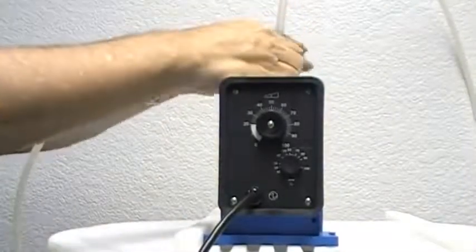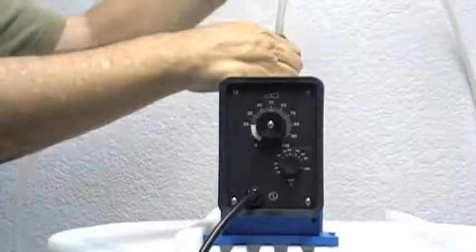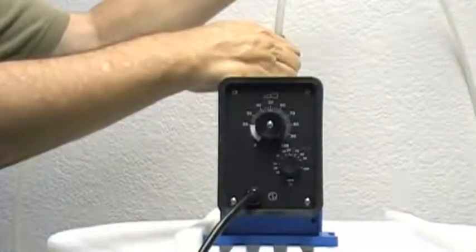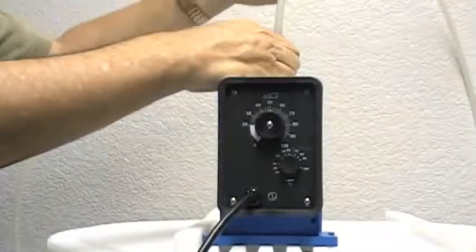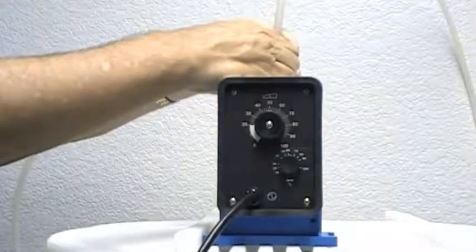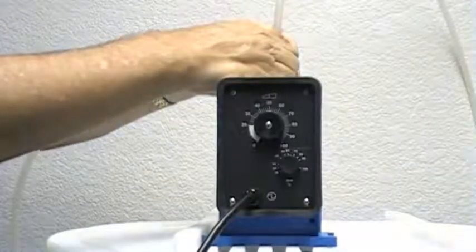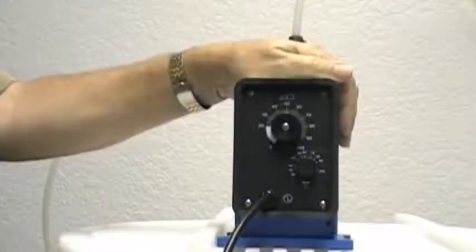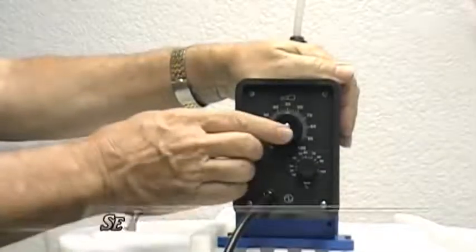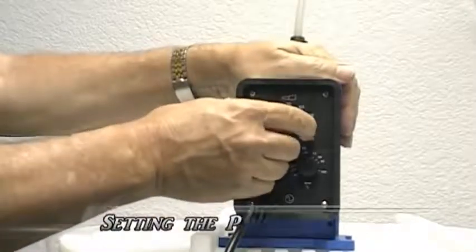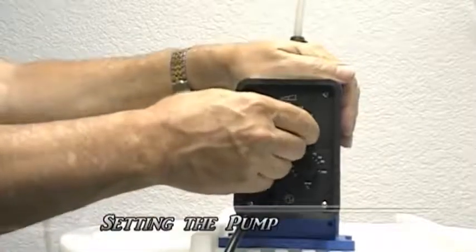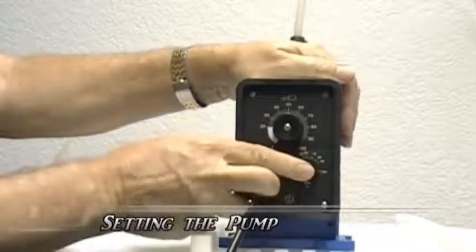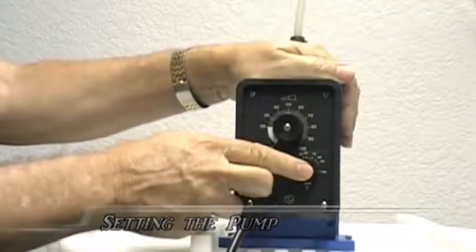This causes the liquid to flow out the discharge side of the bleed valve and into your injector. It may take 1 or 2 minutes for the liquid to fill this line. The Pulsatron A+ pump has 2 adjustments. This adjustment is the stroke length adjustment, and this adjustment is the pulse rate adjustment.